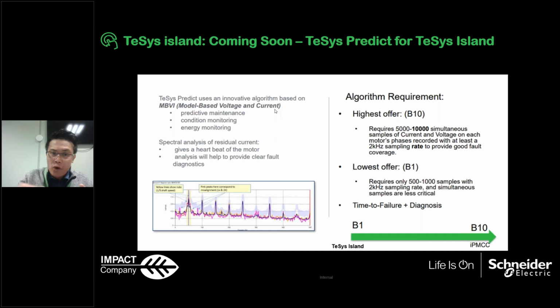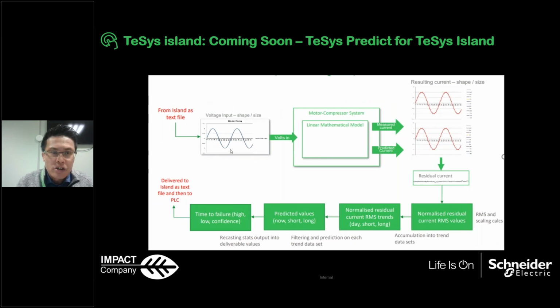What it means is that we measure the voltage, and this voltage will have different disturbances. By measuring this voltage and using a frequency transform to different spectra, we can identify something happening in a specific spectrum. So by monitoring the disturbance of the voltage, we can understand that something has happened or that the motor is failing. Of course, different algorithms have different requirements. For this island we offer the lowest offer, B1, but it's already enough to identify the basic failures of the motors. So the idea is we measure the voltage, do some residual current analysis, transform to different spectra, and then identify the failure of the motors.